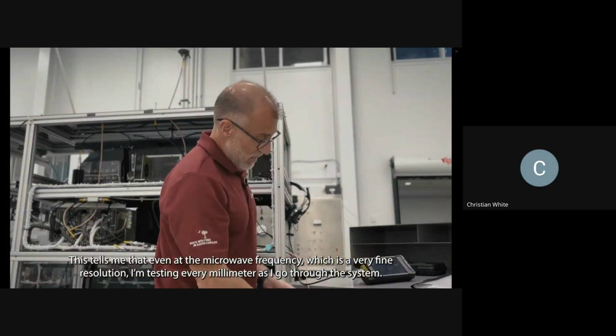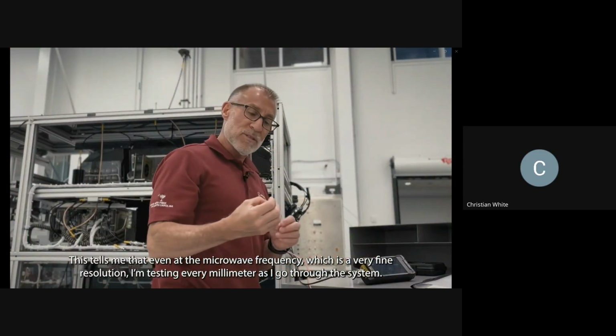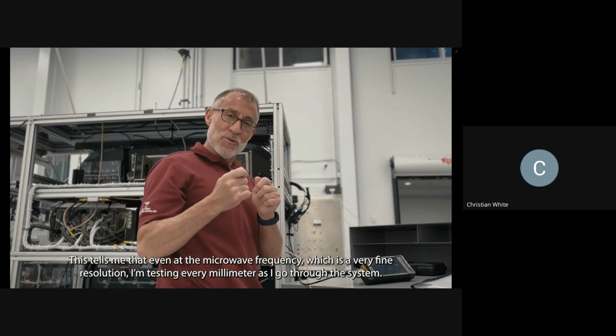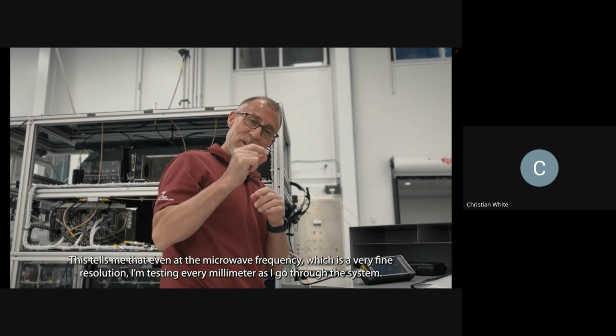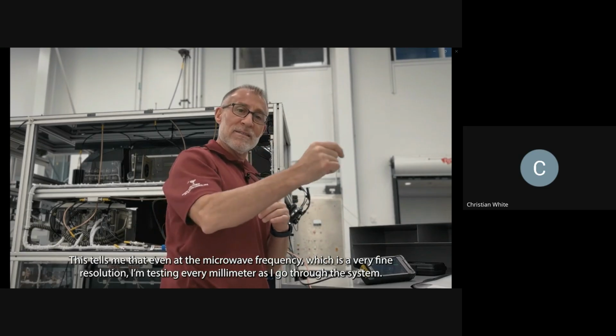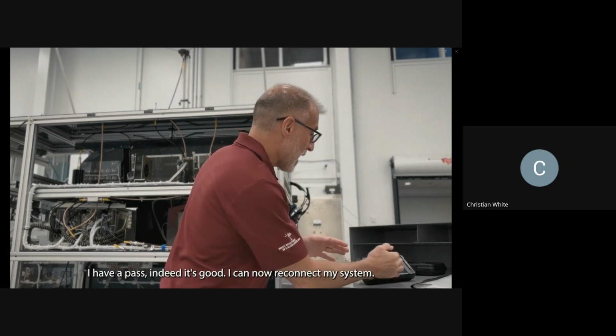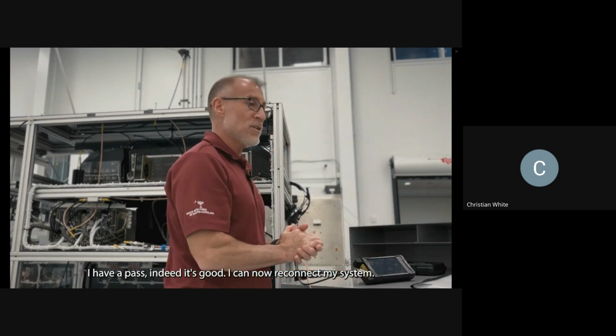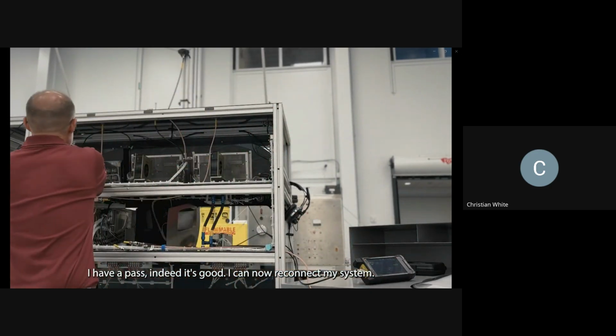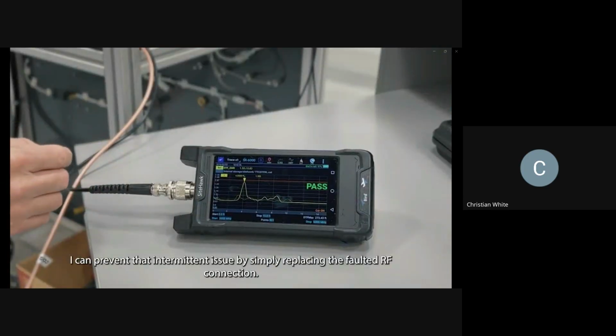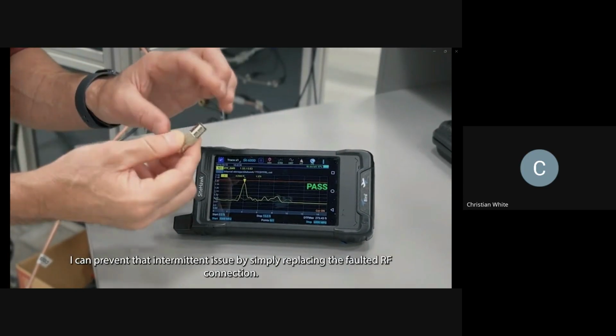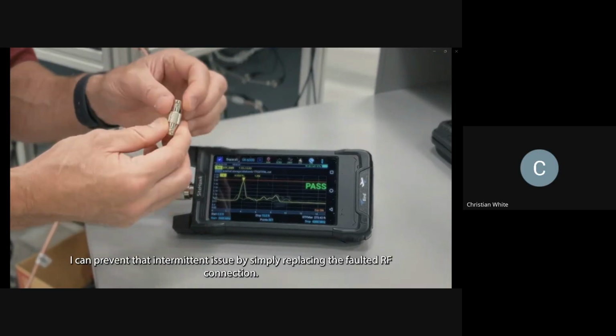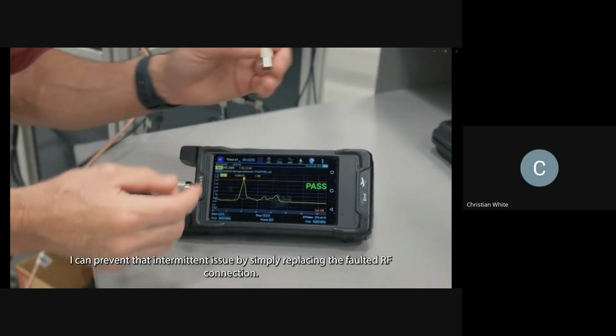This tells me that even at the microwave frequency, which gives very fine resolution, I'm testing every millimeter as I go through the system. I have a pass. It's good. I can now reconnect my system and prevent that intermittent issue by simply replacing the faulted RF connection.